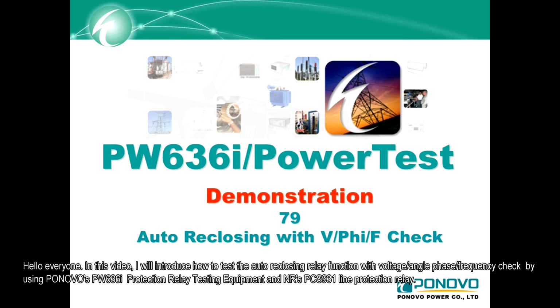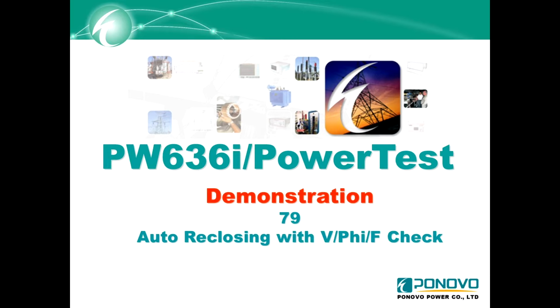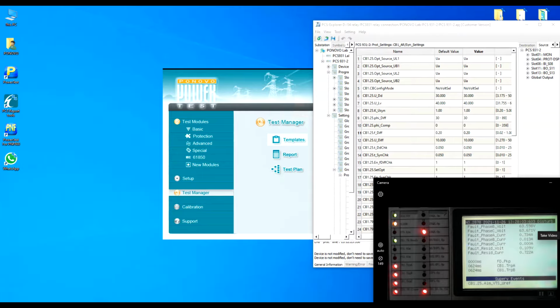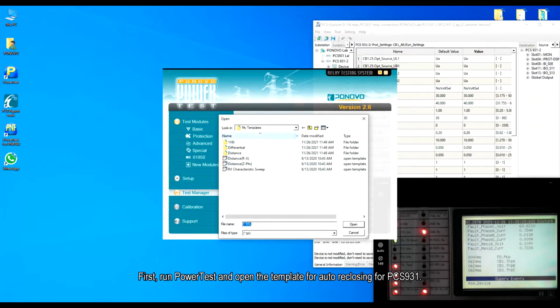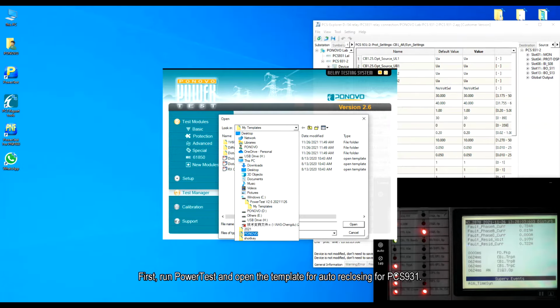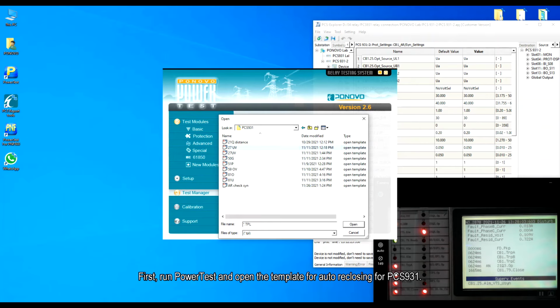Hello everyone, in this video I will introduce how to test the auto-reclosing relay function with voltage, angle phase, frequency check by using PONOVO's PW636i protection relay test equipment and NR's PCS931 line protection relay. First, run Powertest software and open the template for auto-reclosing for PCS931.